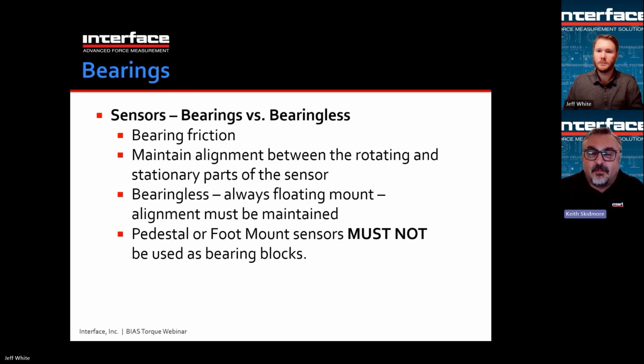So you may have heard me say bearings versus bearingless. Some rotary torque sensors don't have bearings, so they have some kind of a stator which has electronics in it and provides power to the rotating assembly, but there are no bearings to hold those two pieces, the rotating and the stationary piece, near each other. And typically they need to be very close together. So if you have a rotating part and a stationary part, they can't be 20 centimeters away from each other. They have to be held with a pretty close gap. Typically, it may be on the order of 1 millimeter. And so the bearingless sensor has to have some method of holding that sensor and the stator closely together.